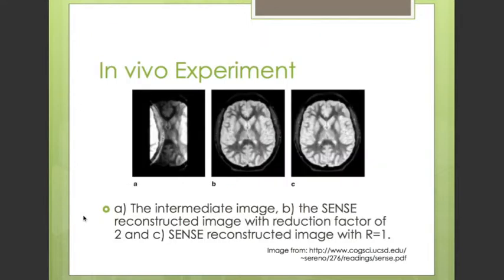An axial brain image was taken with SENSE MRI. Two coils were placed next to the patient's head facing each other. The sequence used was inversion recovery turbo spin echo, with a field of view of 210 mm and a flip angle of 90 degrees. TI was 159 ms, TE was 11 ms, slice thickness was 5 mm, and there were 17 echoes per echo train. The image depicts: A, the intermediate image; B, the SENSE reconstructed image with reduction factor of 2; and C, the SENSE reconstructed image with R equals 1. Although the SNR is reduced in R equals 2, there are no visible artifacts or drop in quality.